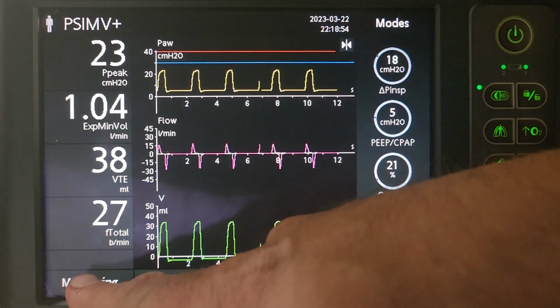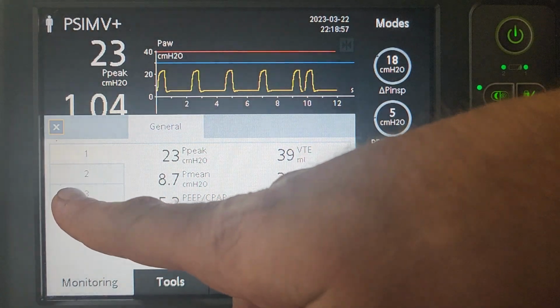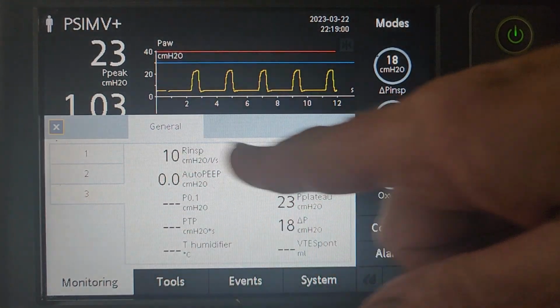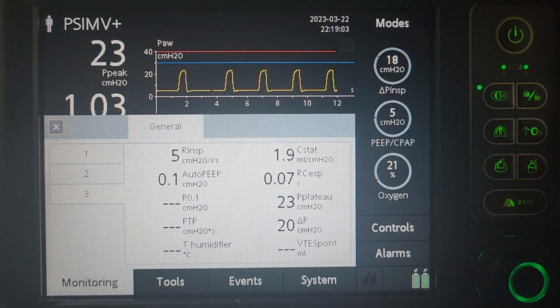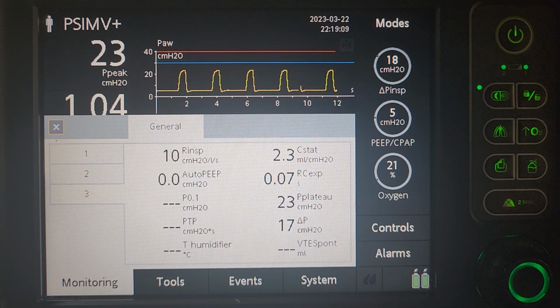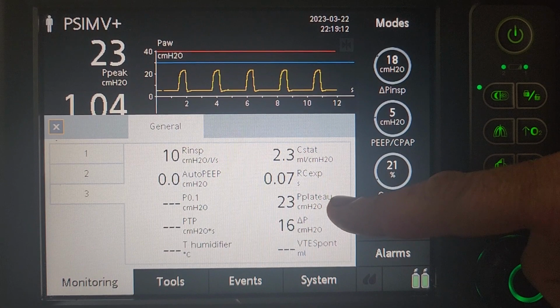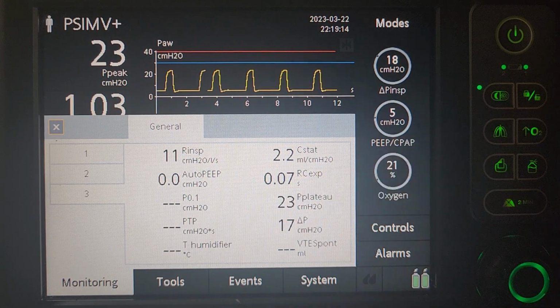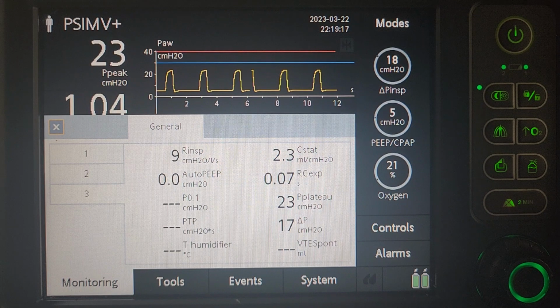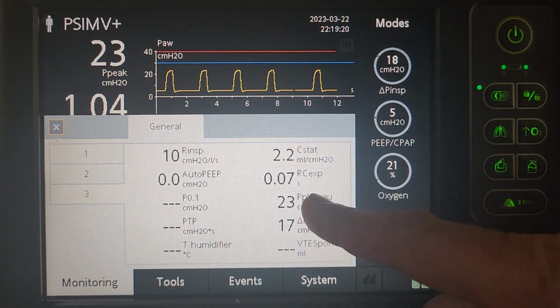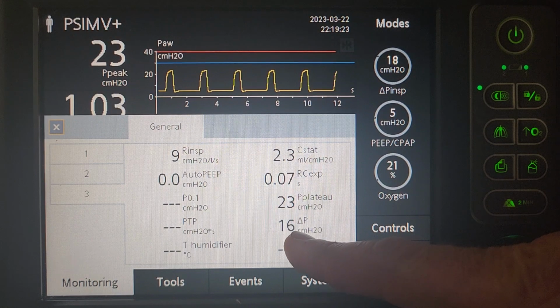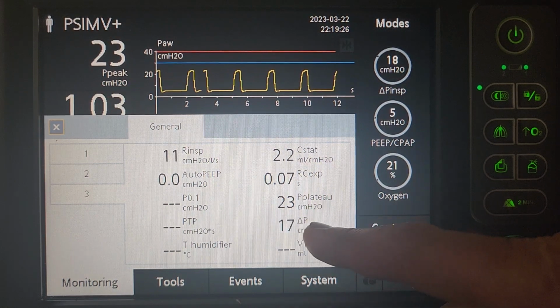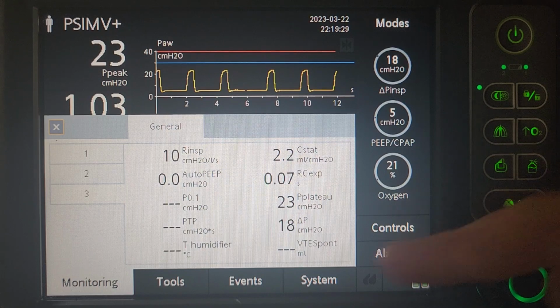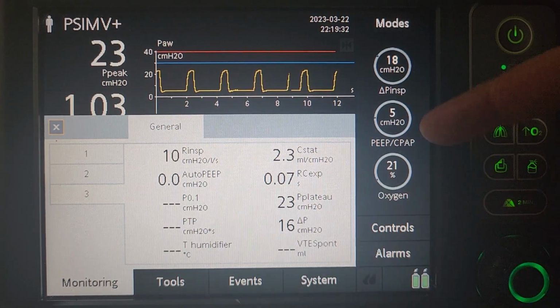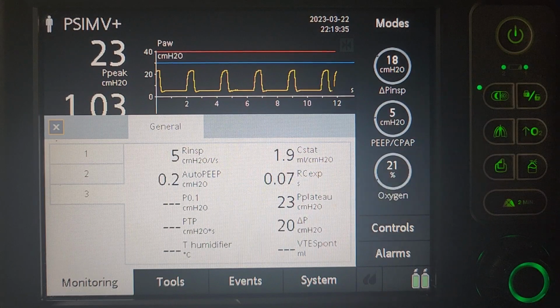So if we go into monitoring over here, the lung that I'm using is not good for the inspiratory resistance and C-stat, so we will ignore those. With our pressure modes, a lot of times you can get a good plateau pressure here, but if it's showing the 3 dashes, what Hamilton suggests, and it's actually in Hamilton's manual, if you look just below your plateau pressure, and this works with adults and pediatrics, you'll see that 16, there's a little delta sign, that's your driving pressure. On the Hamilton, if you take your driving pressure and you add your PEEP, it gives you your plateau pressure.